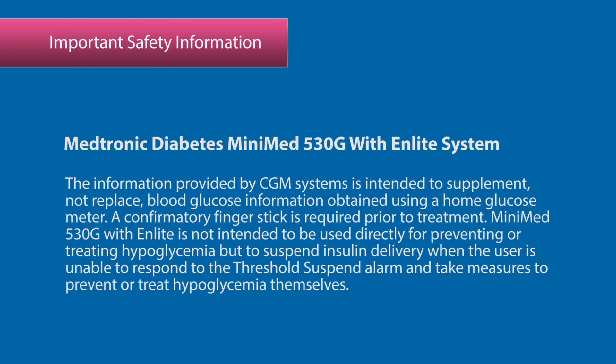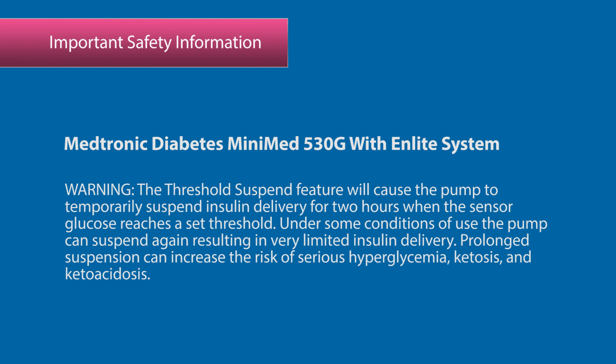The MiniMed 530G with Enlite is not intended to be used directly for preventing or treating hypoglycemia, but to suspend insulin delivery when the user is unable to respond to the threshold suspend alarm and take measures to prevent or treat hypoglycemia themselves. Warning: the threshold suspend feature will cause the pump to temporarily suspend insulin delivery for two hours when the sensor glucose reaches a set threshold. Under some conditions of use the pump can suspend again, resulting in very limited insulin delivery. Prolonged suspension can increase the risk of serious hyperglycemia, ketosis, and ketoacidosis.